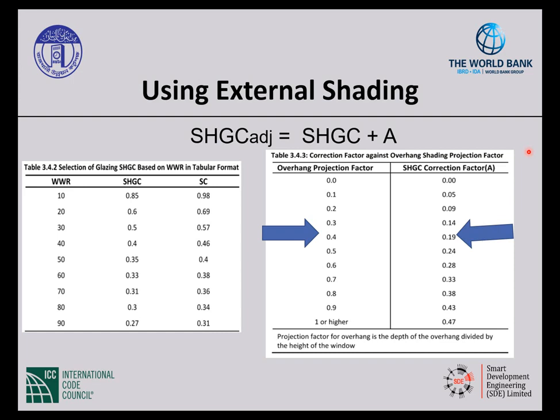Perfect. So let's look at the examples that we were using earlier where we had 50% window to wall area that we calculated. If we had 50% window to wall area, we automatically needed a 0.35 solar heat gain coefficient. That's without shading it. But now we come over here and we say that we shaded it. So we can take that 0.35 and add 0.19 to it and see that now, since I'm shading my window, I can have a window solar heat gain coefficient of 0.54. There's a huge difference, not just in the amount of heat that comes in, but the cost of that window from a 0.35 to a 0.54. So I can now put in a little bit worse window because I'm shading it and I'm only doing 50% windows. That's what it's looking at, all of it holistically.